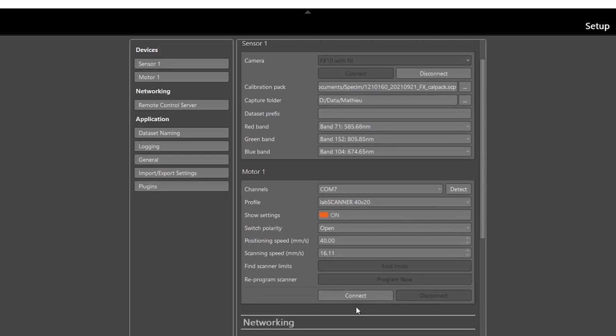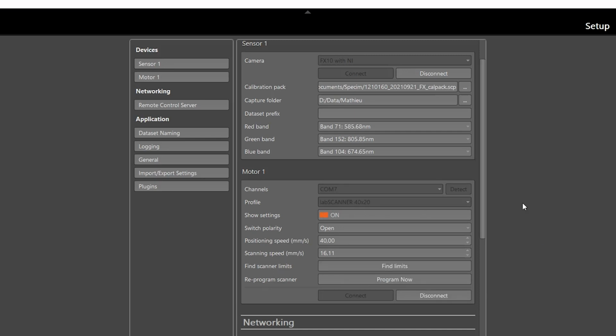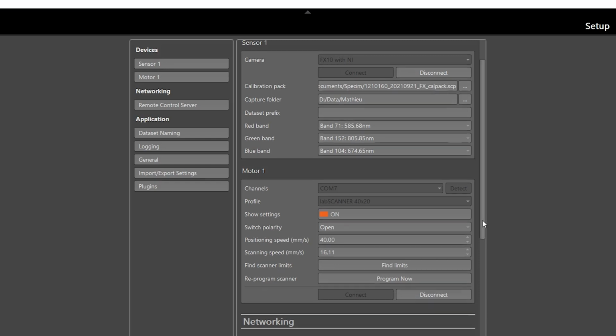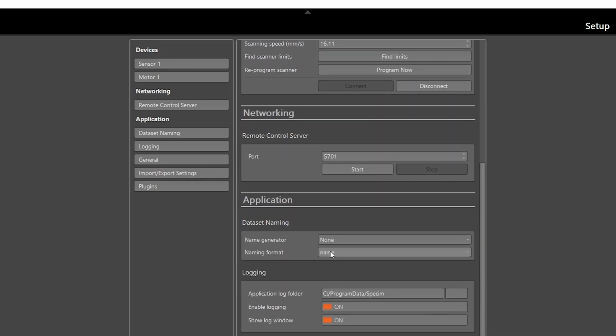Lumo Scanner is an acquisition software to adjust the acquisition parameters with the camera, but also with the scanner. And here you have multiple choices. Now I selected the lab scanner 40x20, but we have different types of scanners. Behind me, for example, we have the 100x50, and we also have other ones, rotary scanners as well. So here I just selected the right one. Then below that, there is a name generator. Here you can choose if in the naming you want a timestamp, a counter, or just the name, and this is what I'm going to choose.